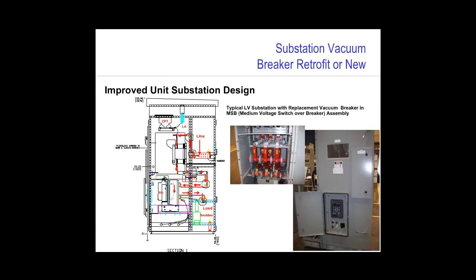Here we show some photos of this same assembly. It's available in either a NEMA 1 or an outdoor NEMA 3R enclosure. And you can see from the pictures that from the rear of the cabinet the snubbers are mounted in the lower section, and you can see the bus runbacks with the current transformers. And finally on the right from the front, there's a door-in-door application that allows easy access to the primary protective relay, breaker control switch, and indicating lights.